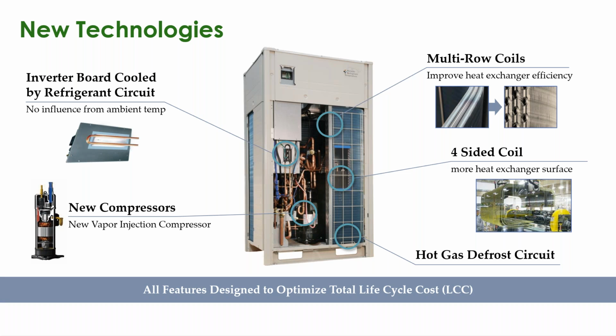The other thing that has been added over the years is many manufacturers are using a hot gas defrost circuit to heat the lower portion of the coil in the pan to aid in defrost water shedding without having to add additional resistance heat to the outdoor unit. All of these features have been added to enhanced capacity systems to optimize the total life cycle cost of the system and allow more flexibility in design for cold climates.